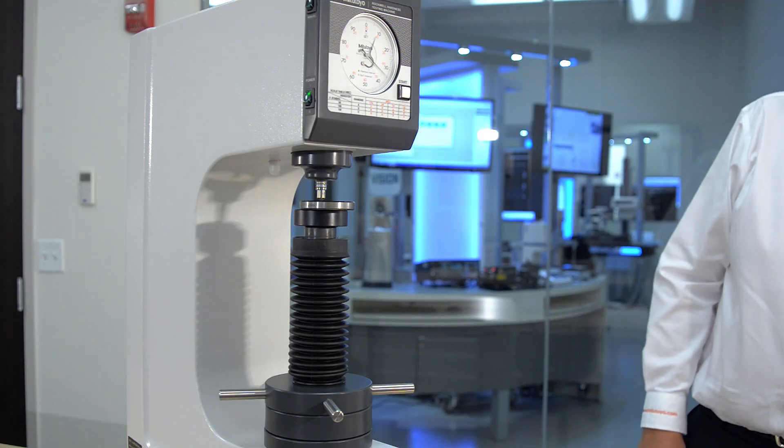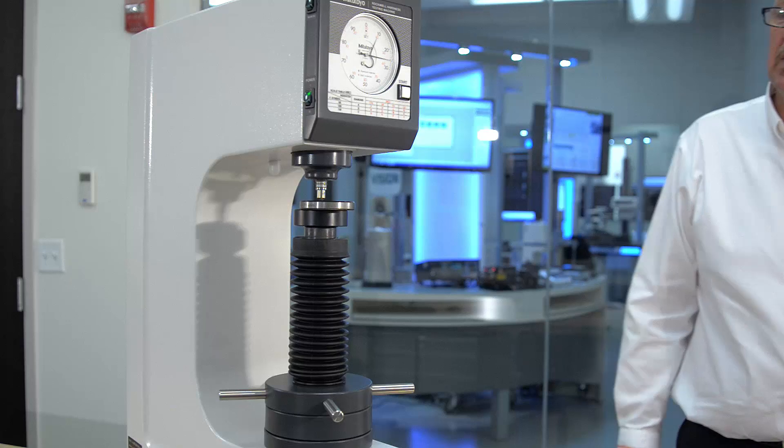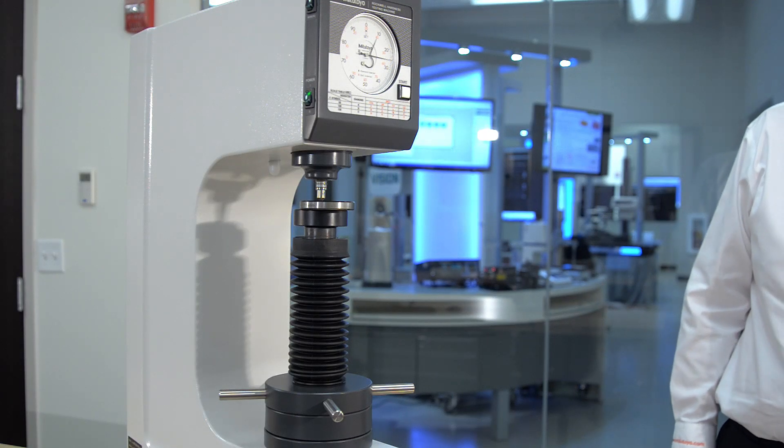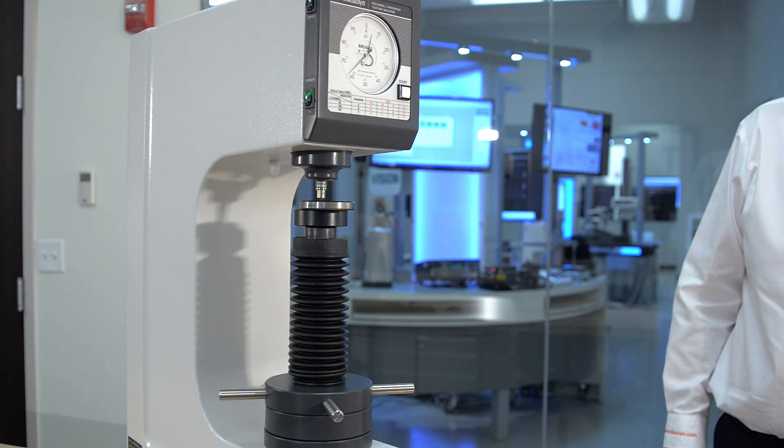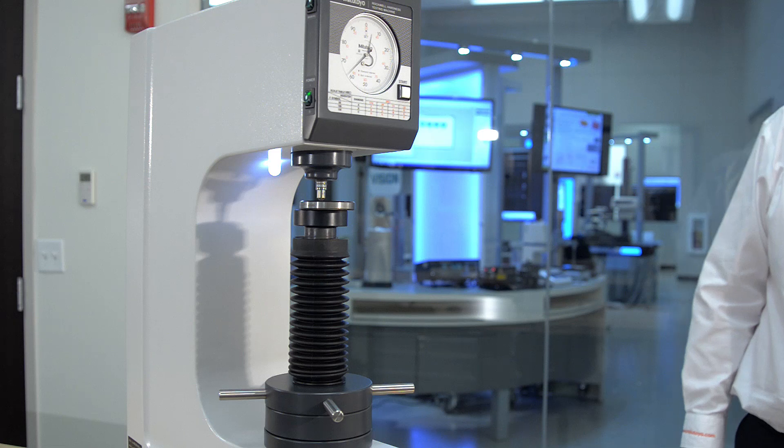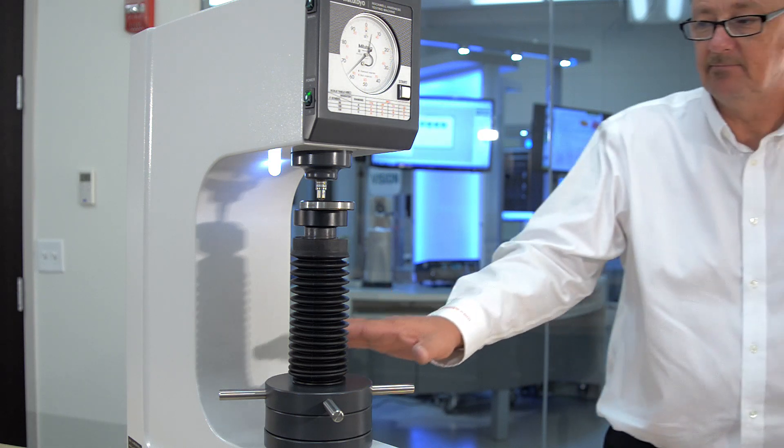uses a motor to apply and remove the major test force instead of the oil dashpot system found in some inexpensive imports. This ensures that operator influence is reduced and tests run much more consistently.